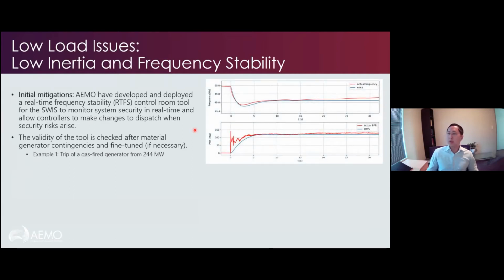Here are some examples of the predictions that the RTFS has made versus actual frequency response. This is a 244 megawatt gas-fired generator trip, and the RTFS has fairly well predicted the actual frequency response. And it's nice, obviously, that it's a bit more conservative, and so far it's always been a little bit more conservative than actual responses. We do get IPP responses in the actual frequency response. As you can see here, this is the actual primary frequency response, and there's more happening from an IPP's perspective than what you would expect from what we predict, where we only use what we can rely on in terms of contracted spinning reserve.